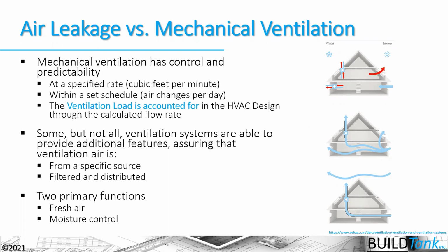But we need to remember that the primary function of mechanical ventilation is to bring in fresh air for the occupants and to provide background moisture control. So if you're seeing condensation on your windows in the wintertime, it's probably a ventilation issue. We're not controlling the moisture content inside the house well enough.